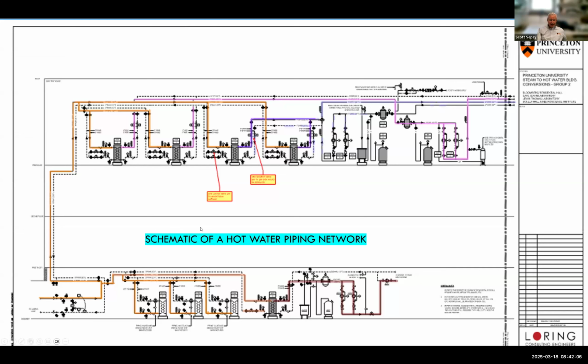So this is a schematic of the final design of a system in one of our science buildings. And here the orange line is the primary district hot water system coming in. It always goes to heat exchangers where we intercept and divide the building systems from the district system for chemistry and pressure reasons. But here in the basement, they go to domestic and lab water heat exchangers. Upstairs, they go to hot water systems for reheats and a boosted glycol heat recovery system where we try to pull heat out of the exhaust air and add a little more heat as we need through a heat exchanger into the glycol. So really, there's 4 different hot water systems here in this science building. We monitor, we have flow meters at the building entrance, differential pressures that inform the plant of what's going on with the district system. And that's typical for every building.